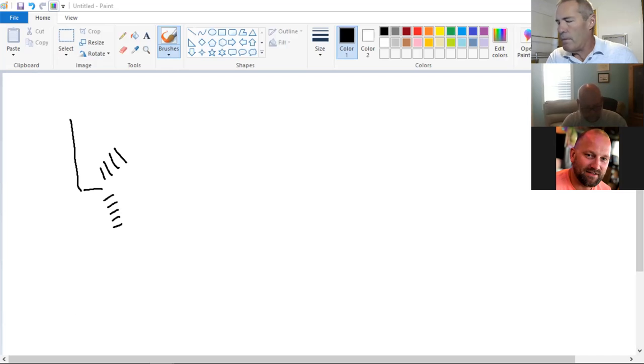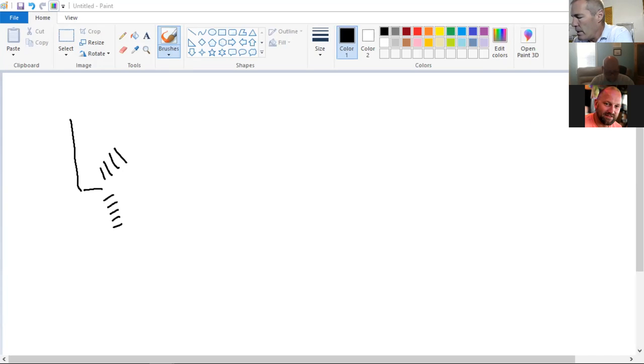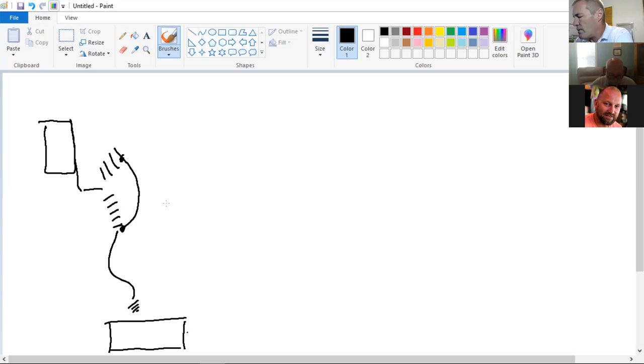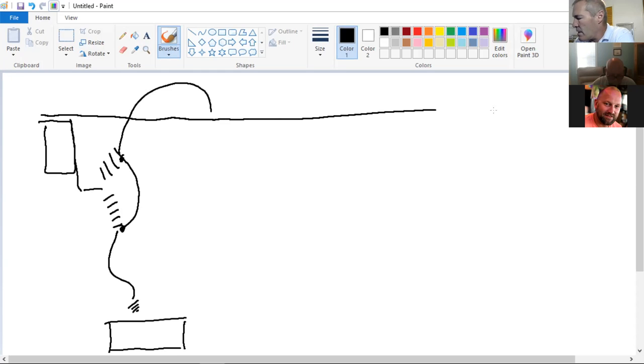All right, so you'd have a cross arm and a switch mounted on it, and here's the fuse that's inside the switch. Then you have your wire going down to your transformer, like this small transformer. This wire comes up, and you'll see in our construction build today, it comes up and makes contact with the primary wire, so you're able to get primary voltage down to the transformer, just like that.